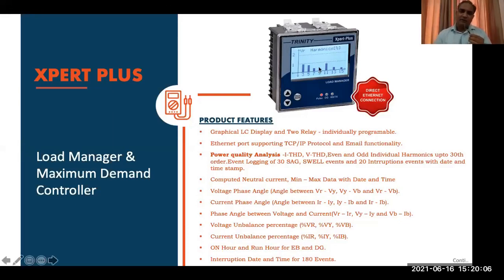Apart from this meter having a complete customized LCD display, wherein you can see on one of the screens the bar graph also showing, it will give you power quality analysis, current harmonics and voltage harmonics up to the 30th level for both odd and even, and event logging for 30 SAG events, 30 swell events, and 20 interruptions with date and timestamps.